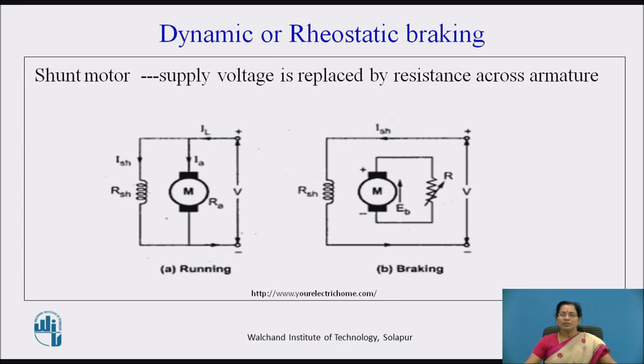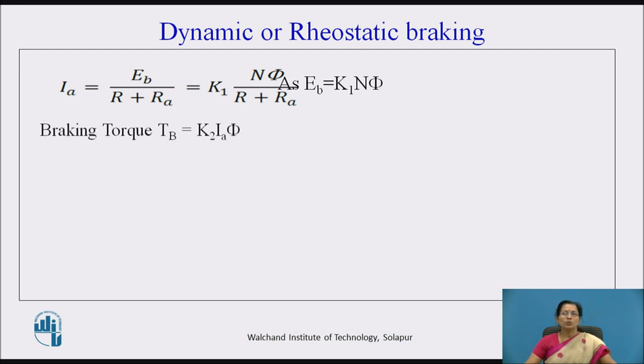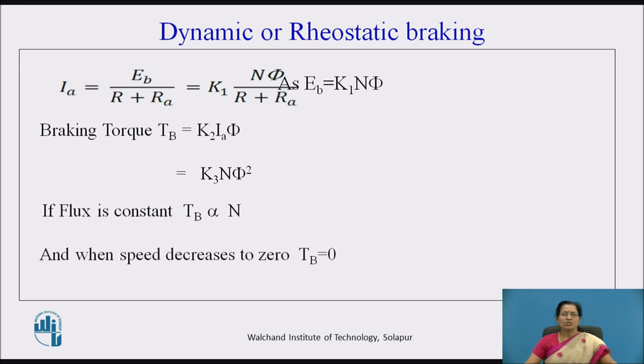The torque created on the motor is now reversed and braking is applied. The armature current is given by I_A = E_B / (R + R_A), where E_B = K1 * N * φ. The braking torque equals K2 * I_A * φ. Substituting I_A, the braking torque equals K3 * N * φ². If flux is constant, braking torque is directly proportional to speed, and when speed decreases to zero, braking torque also becomes zero.